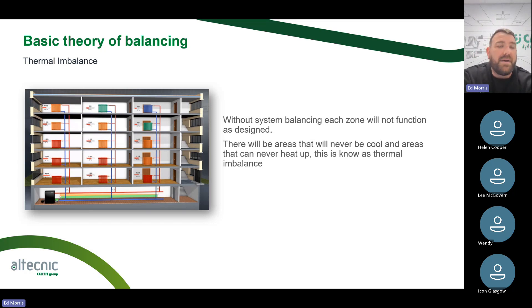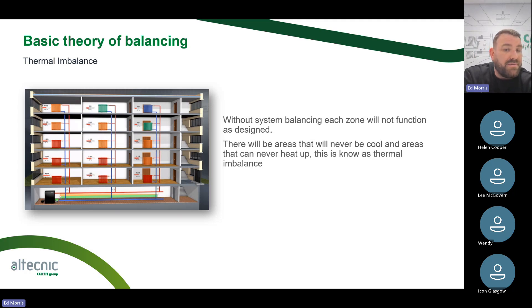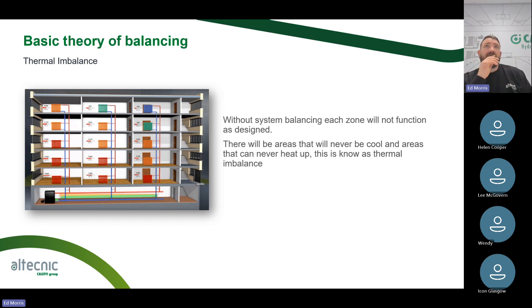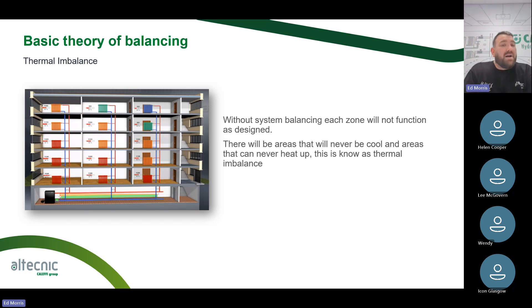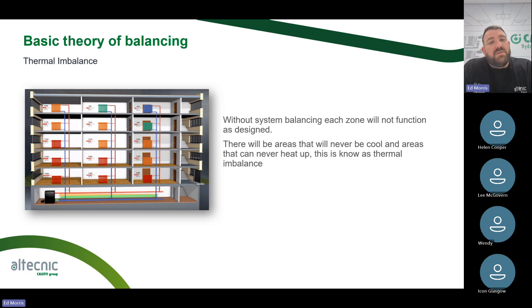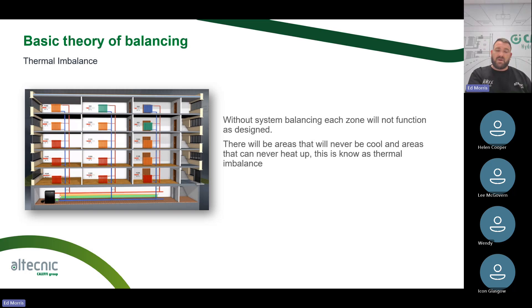In a slightly different diagram, the red panel radiators are getting really, really hot and will probably never cool down because we cannot restrict the flow through there. The pump is pushing hot water through those panel radiators and they'll run at 120% load. The orange band going through the middle will give a relative temperature. The two green radiators towards the top right-hand corner are probably the best balanced in the system — but having only two out of that many balanced is not right. We need to slow water going through the red and orange radiators and push it towards the green and blue zones.